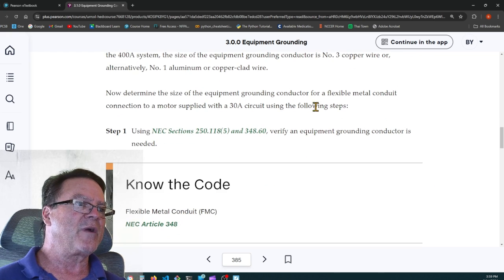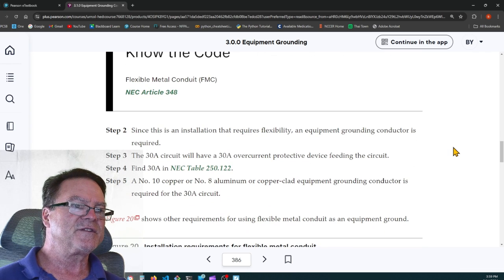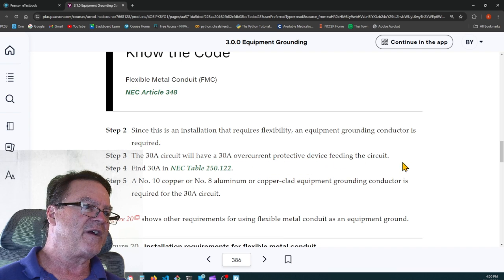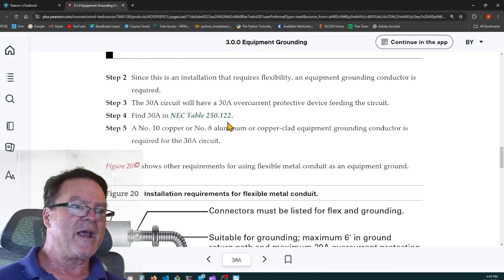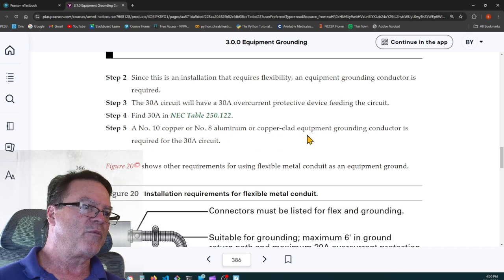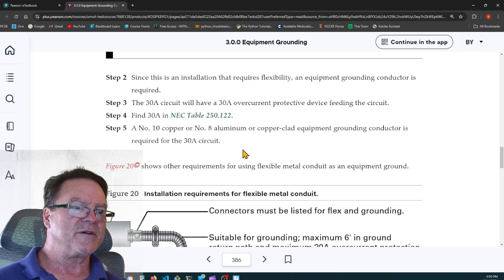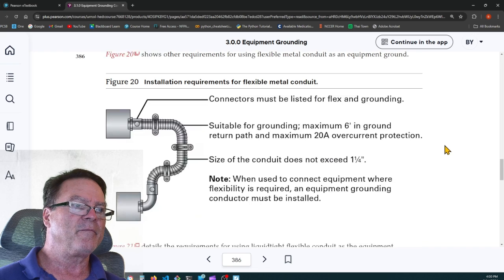Now determine the size of the equipment grounding conductor for a flexible metal conduit connection to a motor supplied with a 30 amp circuit using the following steps. So they'll do the same thing. They'll find the overcurrent protection device. It says this 30 amp circuit will have a 30 amp overcurrent protective device feeding the circuit. Find the 30 amp in table 250.122, a number 10 copper or number 8 aluminum or copper-clad aluminum equipment grounding conductor is required for the 30 amp circuit.